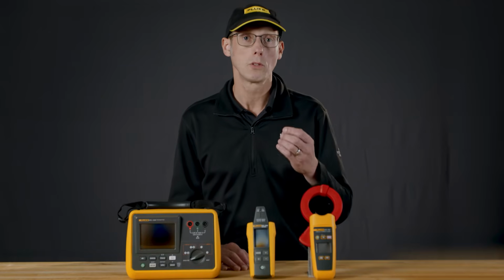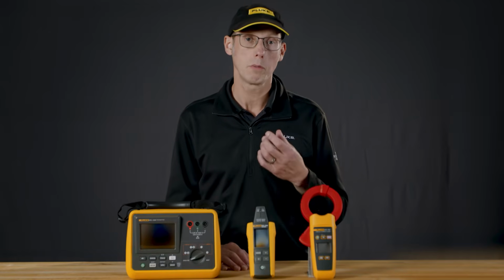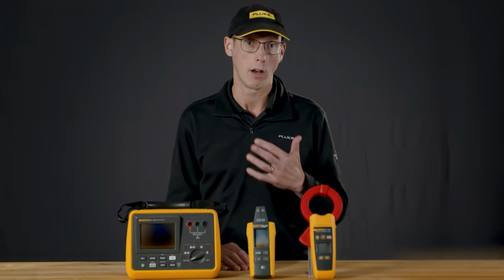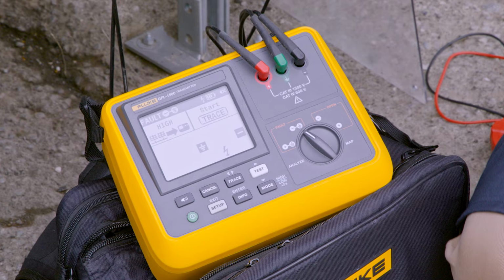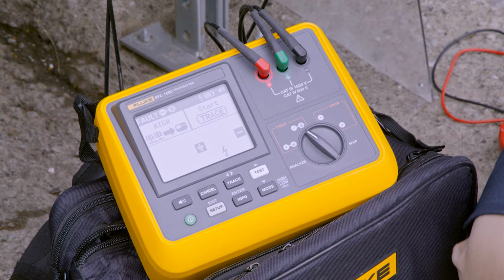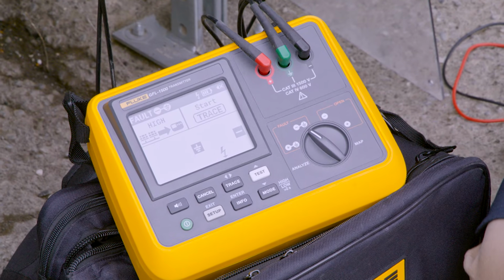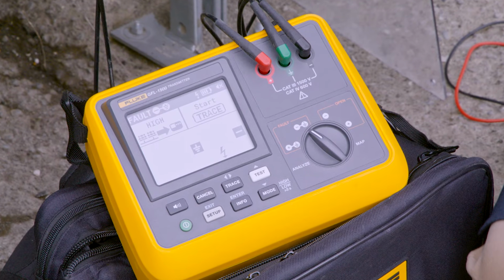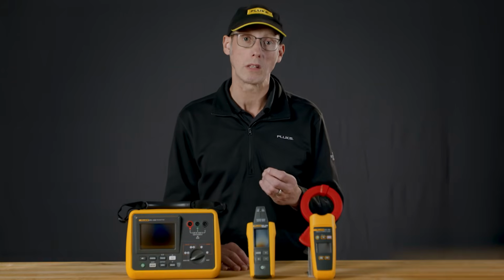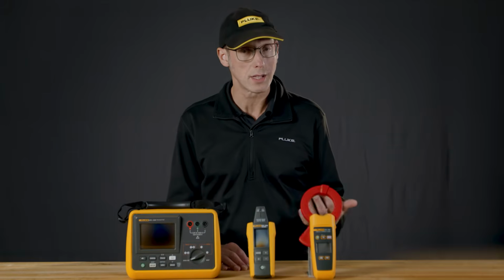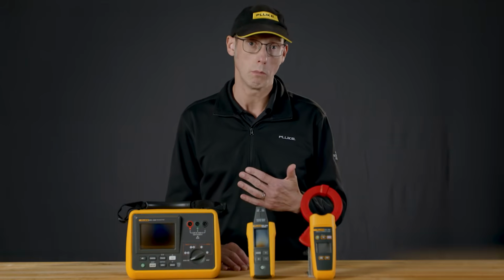In order to be able to use array mode, there has to be voltage present between whatever side you're injecting on and the ground. The unit will have a lightning bolt if it is receiving more than 30 volts on whichever fault mode that you are using. So you need that lightning bolt present in order to use array mode. If the lightning bolt is not present, then switch to unit mode.